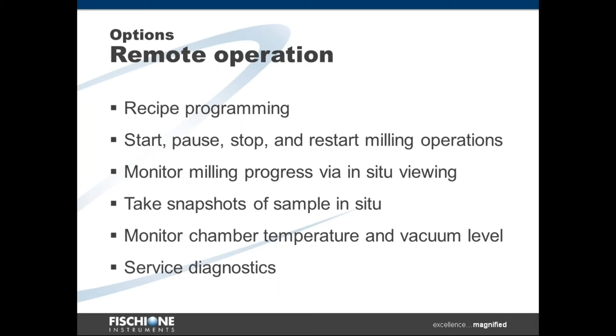Remote operation is something that we feel has been increasingly important, particularly in this day where many laboratories are shut down. The remote operation of the ion mill allows for recipe programming, starting, pausing, stopping the milling process, monitoring the progress via the microscope options, taking snapshots when desired, and also monitoring all of the important instrument functional parameters, such as chamber pressure, vacuum level, and sample temperature. There's also a service diagnostics component that allows the Fischione service team to access the instrument for diagnostic purposes.